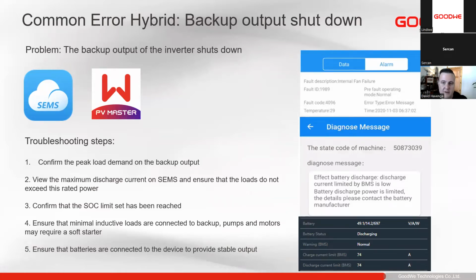Next, we have some common errors that we will go through. First of all, we can diagnose this from SEMS as well as PV Master. This error is the backup shutting down of the inverter, especially in countries like South Africa, where we use the backup of the inverter constantly. Very often we can have the backup shutting down, and that can be for many reasons. First we need to confirm the peak load demand. As I said, in the curve on SEMS portal, we can go there and view the peak demand. I'll show you an example of that shortly.